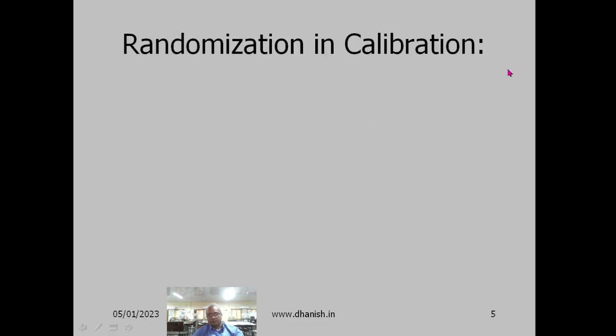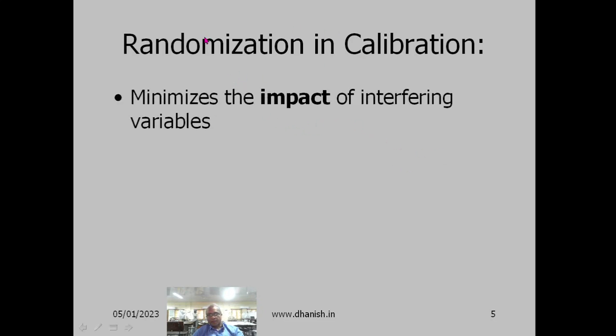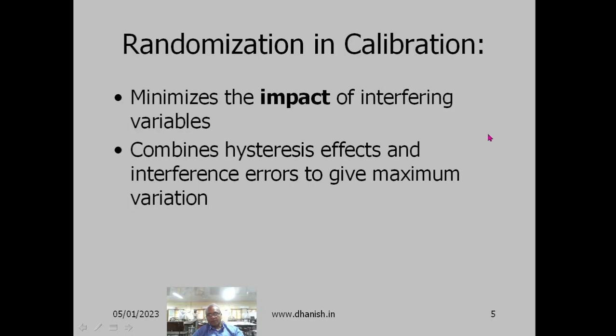In calibration experiments, where we try to calibrate one instrument using certain standard values, by carrying out the experiment in random order, the impact of interfering variables is minimized — not eliminated, but minimized. During calibration, when you take readings in increasing order and then in decreasing order, there will be a difference — that is called the hysteresis effect. Those effects and interference errors get mixed up with the effect due to extraneous variables to give maximum variation.